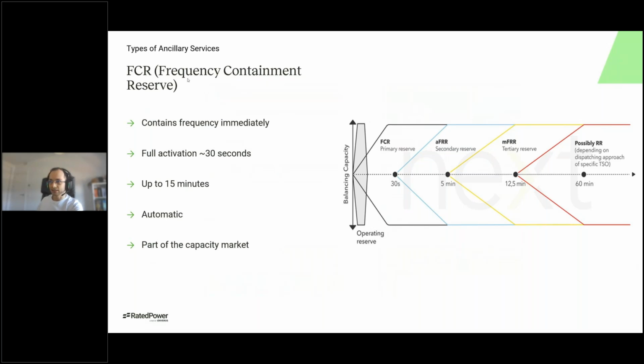The objective of this is to contain the frequency immediately, so that the big drop that we saw before, this FCR will just jump into place and try to contain this frequency drop. It's very fast. The full activation is achieved at around 30 seconds, but it starts providing services almost instantly. It can work up to 15 minutes. It gets triggered automatically. Otherwise, I think humans are not as fast to react to this. And it takes part in the capacity market.